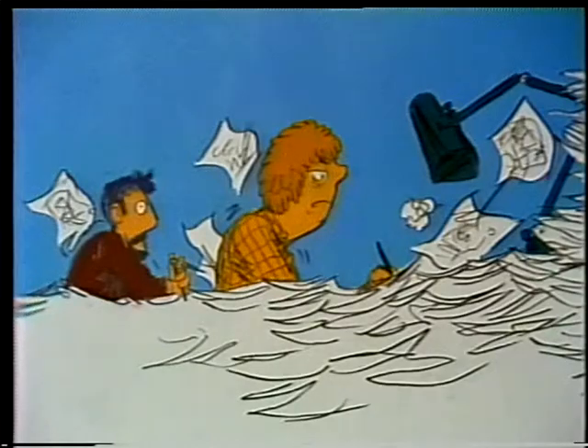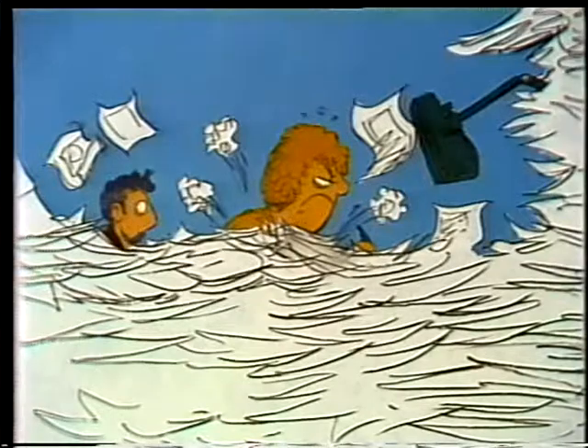We've learned what pressure is and what it can do when it gets out of hand. We've looked at the most simple type of pressure relief device, the rupture disc. We've seen that although a rupture disc is effective, fairly inexpensive, and requires only minimal maintenance, it has one major drawback. When a disc does burst, the system usually has to be shut down to replace it. This disadvantage of rupture discs sent designers back to their drawing boards to find more versatile pressure relief devices. We'll see one of the devices they came up with in the next segment.